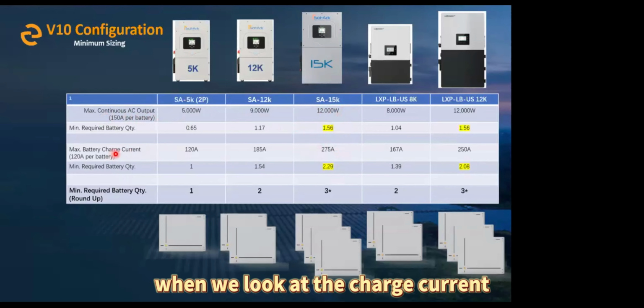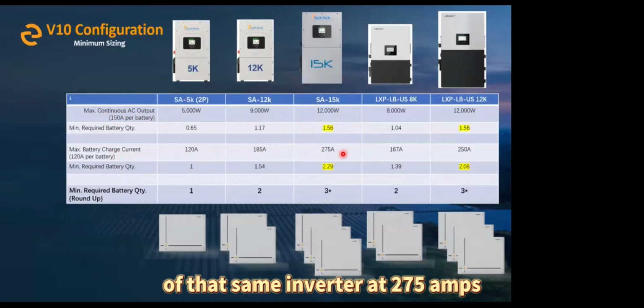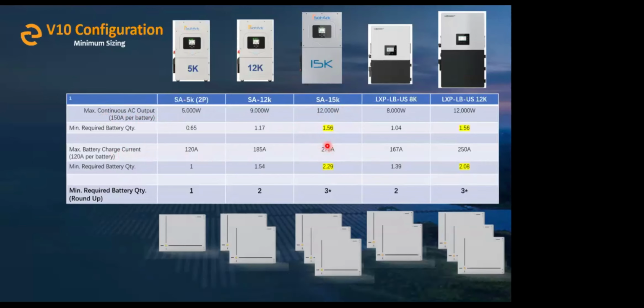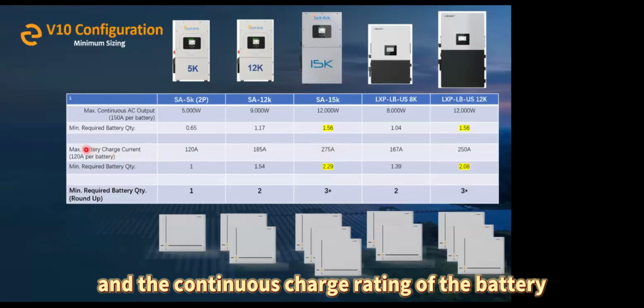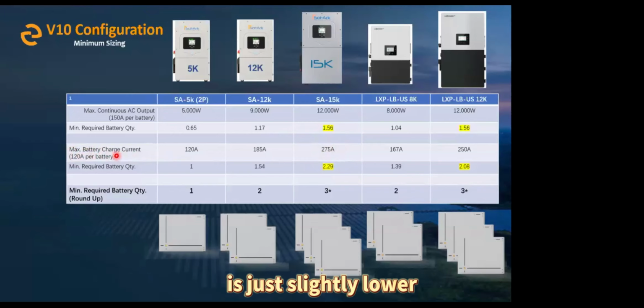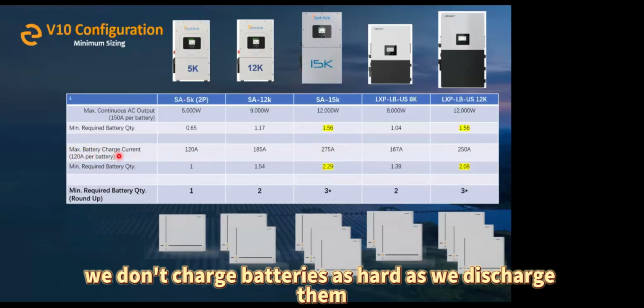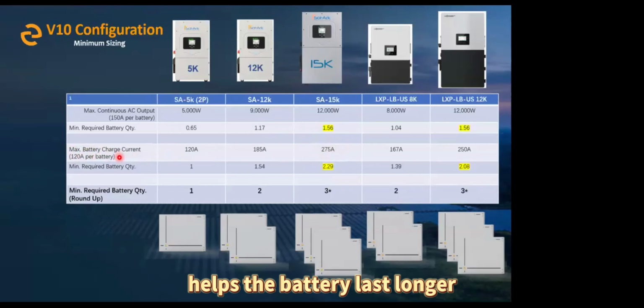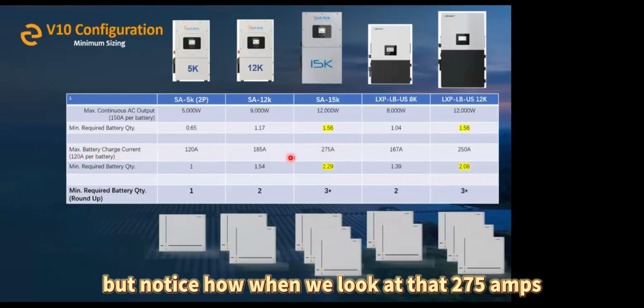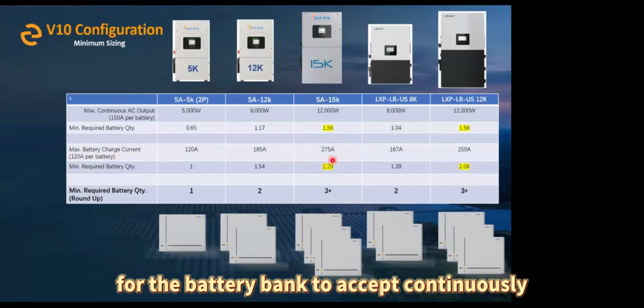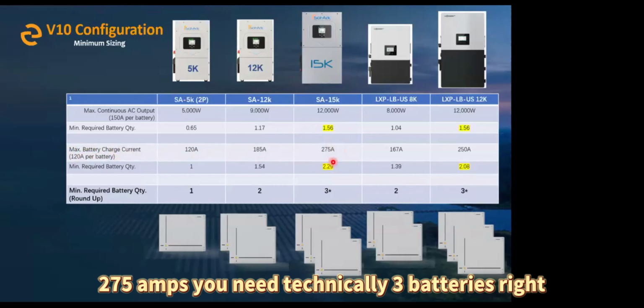When we look at the charge current of that same inverter at 275 amps, the continuous charge rating of the battery is slightly lower. Usually we don't charge batteries as hard as we discharge them, it's easier on the cells and helps them last longer. But notice that for the battery bank to accept 275 amps continuously, you technically need 3 batteries.